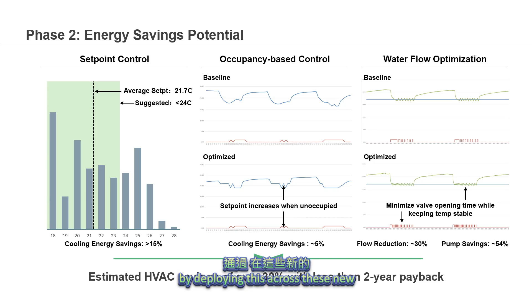So there's occupancy-based control, where if there's people in the room, you can see that we change the set point down. If someone leaves the space, the temperature jumps up versus the baseline. And finally, there's water flow optimization, where you can see how the water flow, or the valve, opens and closes in the baseline condition. The temperature is held steady, but here we're opening it much less, at a higher frequency. You can keep the temperature just as steady, but you're using 30% less flow, and saving about 50% pumping energy. So we think that by deploying these new methods across the entire campus, we can reduce up to 30%, with less than a 2-year payback.